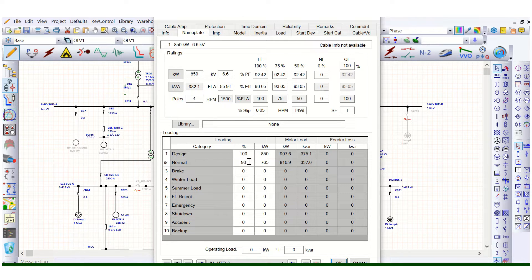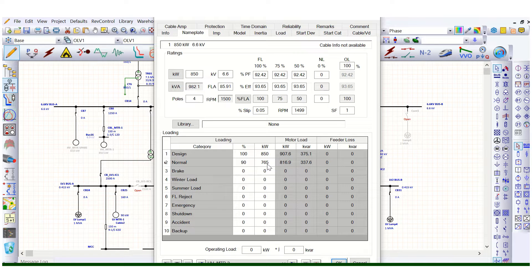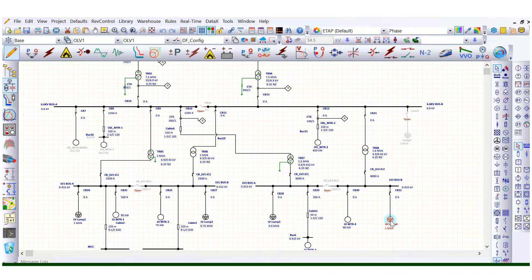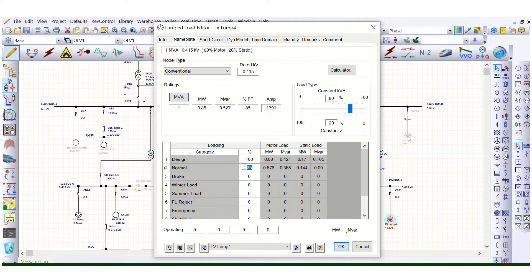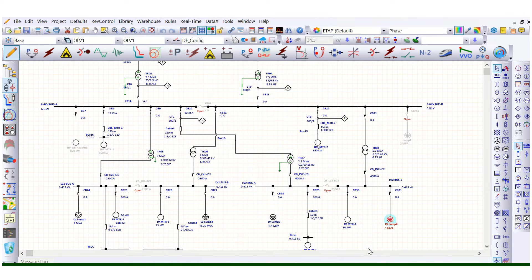Under normal conditions, let's say this is 90 percent of 850 kilowatt, so this is coming to 765 kilowatt. This is applicable for all other loads as well. For the lump load, the design load is 0.68 megawatt, 680 kilowatt, and this is 100 percent. At 85 percent of that, this is coming to 0.578 megawatt. So this is the absorbed load and this is the connected load as per the load list.